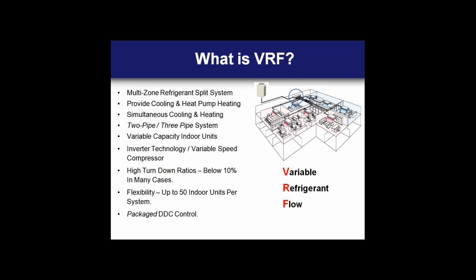Unique to these systems is also variable capacity control at each of these DX coils. They have smart coil technology. So each of these units will have a linear expansion valve, basically a pulse needle valve, with up to 2,000 steps of operation. And that provides very precise throttled meter control of refrigerant to each of the indoor units at any given time.